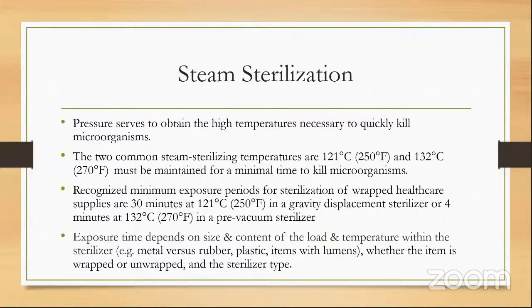The two common steam sterilizing temperatures are 121 degrees Celsius or 250 degrees Fahrenheit, and 132 degrees Celsius or 270 degrees Fahrenheit. And this must be maintained for a minimal time to kill microorganisms. The recognized minimum exposure period for the sterilization of wrapped supplies is 30 minutes at 121 degrees Celsius if we're using a gravity displacement sterilizer, or 4 minutes at 132 degrees Celsius in a pre-vacuum sterilizer. Now remember earlier I said to you that there are different kinds of sterilizers. They do their process in different ways.